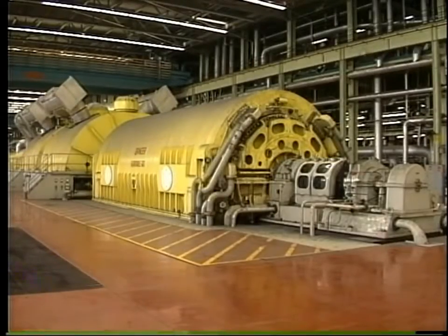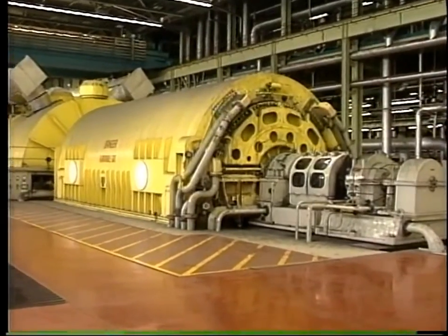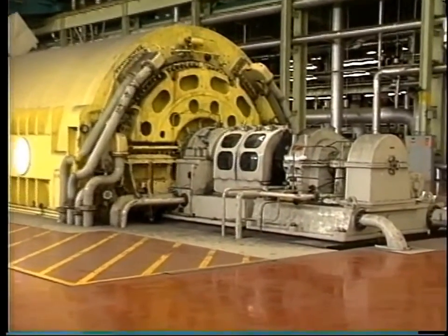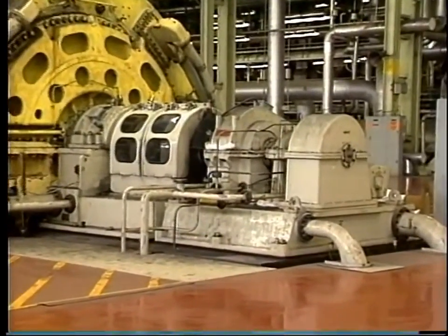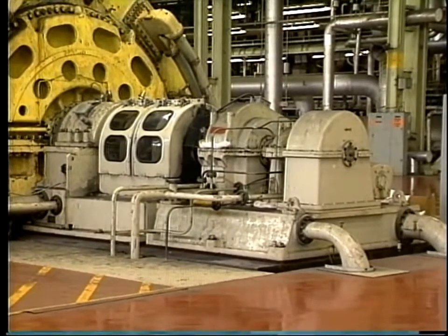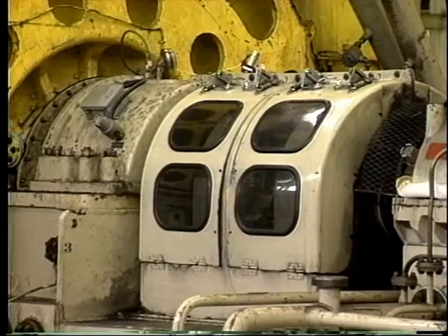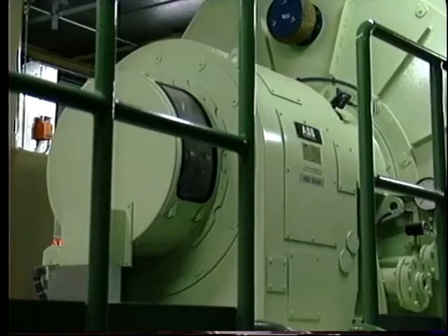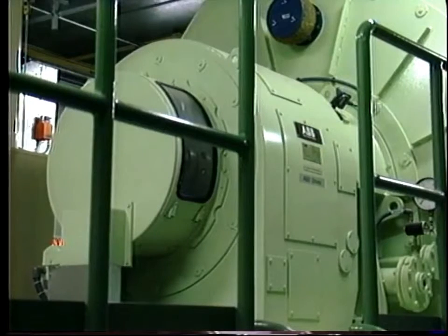An alternative source of DC excitation is from a generator, which may be driven by direct coupling to the shaft, or in some cases through a reduction gearbox. Access is provided to allow maintenance and inspection of the collector rings and exciter. We'll be looking at details of different excitation systems later in this module.